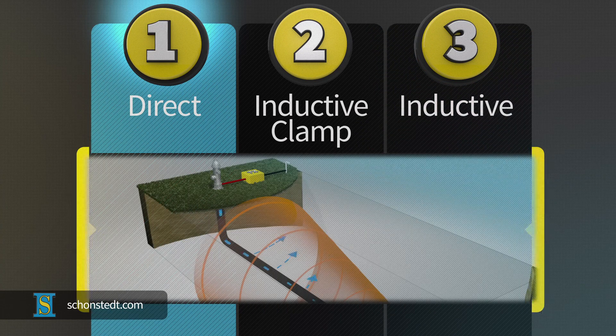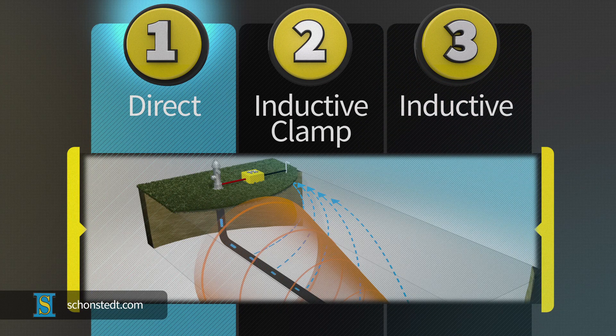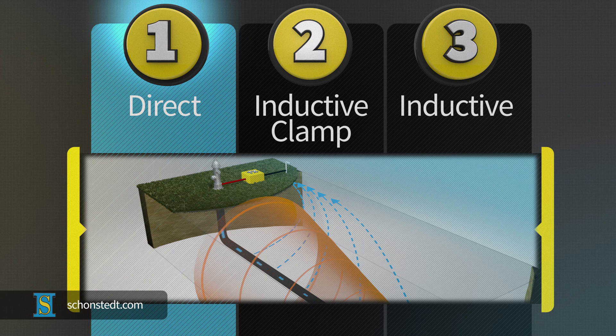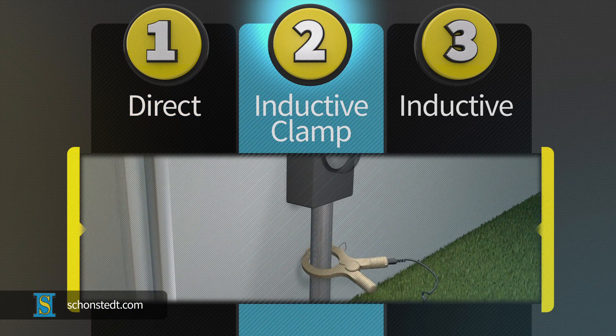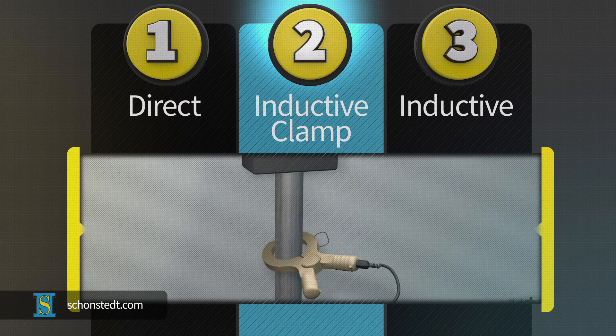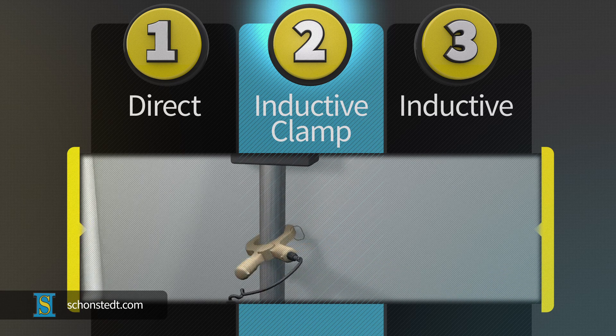The direct mode produces the largest amount of current and increases locating success. The inductive clamp mode produces less current, but it's a good choice when lack of access to the pipe or cable prevents you from using the direct mode.